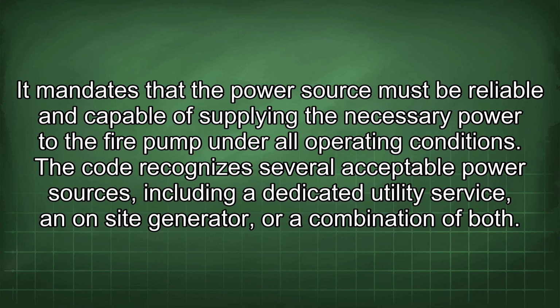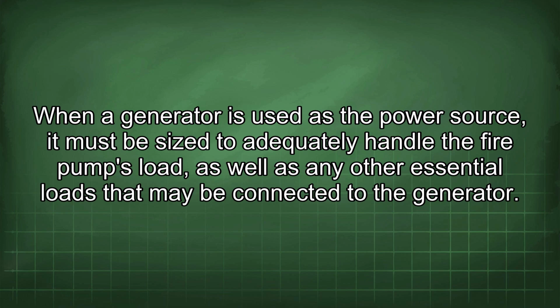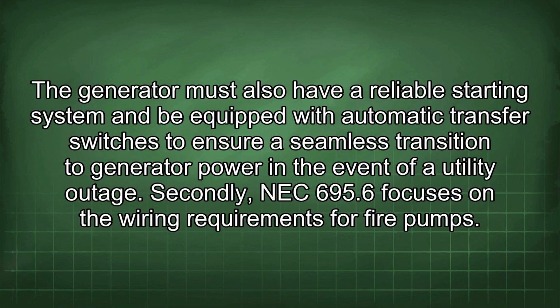a combination of both. When a generator is used as the power source, it must be sized to adequately handle the fire pump's load, as well as any other essential loads that may be connected to the generator. The generator must also have a reliable starting system and be equipped with automatic transfer switches to ensure a seamless transition to generator power in the event of a utility outage.